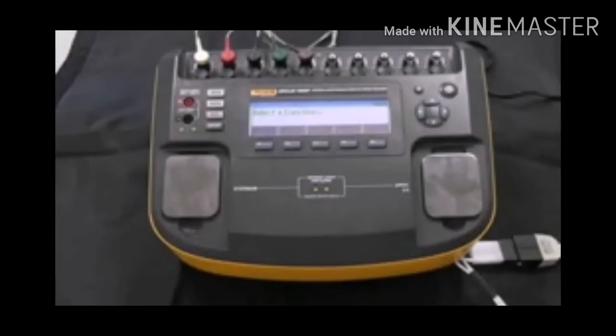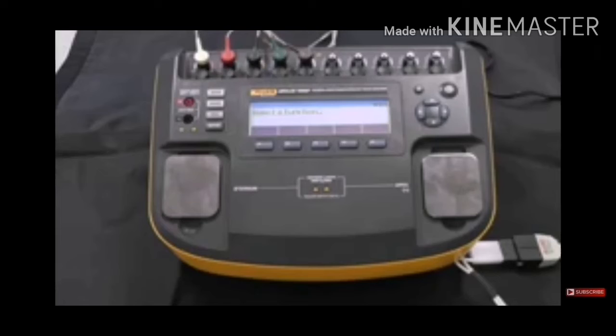Talk to you about the Impulse 7000 defibrillator and pacemaker analyzer from Fluke Biomedical today. This is the Impulse 7000. You can see we have it all set up. We even have some ECG leads connected to it. This unit is designed for testing any defibrillator, including AEDs, and the transcutaneous temporary pacemakers that are integrated into defibrillators.